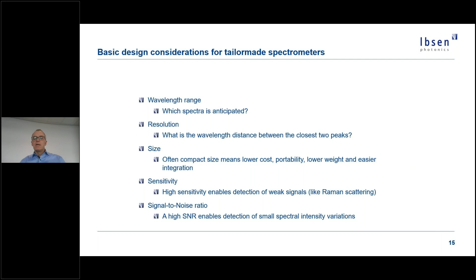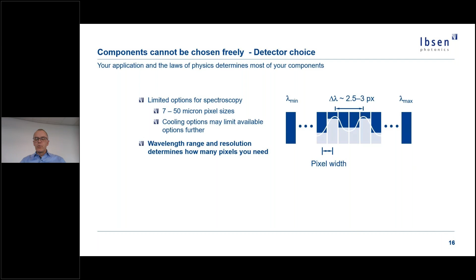So even though a spectrometer consists of several components, they cannot be chosen freely. In fact, the requirements from your application linked with the laws of physics often limit the design choices. Here we consider the detector, and the detector should have enough pixels to resolve the spectrum and the closest peaks in the spectrum. Normally, it's advisable to require 2.5 to 3 pixels to cover the resolution, which we here call delta lambda. On the other hand, we also need enough pixels to cover the entire wavelength range from the shortest wavelength to the longest wavelength. And not just any detector array can be used for advanced spectroscopy like Raman. In fact, the pixel size is often limited to between 7 and 50 microns, and your options will be further limited if you require a cooled detector. The wavelength range and resolution determine how many pixels you need, and let's have a look at an example for that.